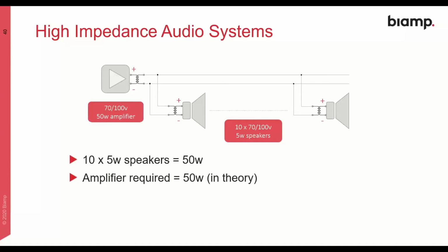Another consideration right here at this design point is, what if the customer comes back to me in 6 months and says, oh, you know what, I really would like to have another couple of speakers on this line somewhere in the room, in the building. So you could, for example, quite easily upgrade the amplifier to a 120 watt design. It would be quite minimal cost now at the head end of the project. But if you tried to change it or add power later on, 6 months down the road, it becomes quite an expensive operation. Whereas if you put a 120 watt amplifier in now, it'll work perfectly with the 50 watt load. And then there's still 70 watts to use for the customer to add more speakers in the future if they need to.